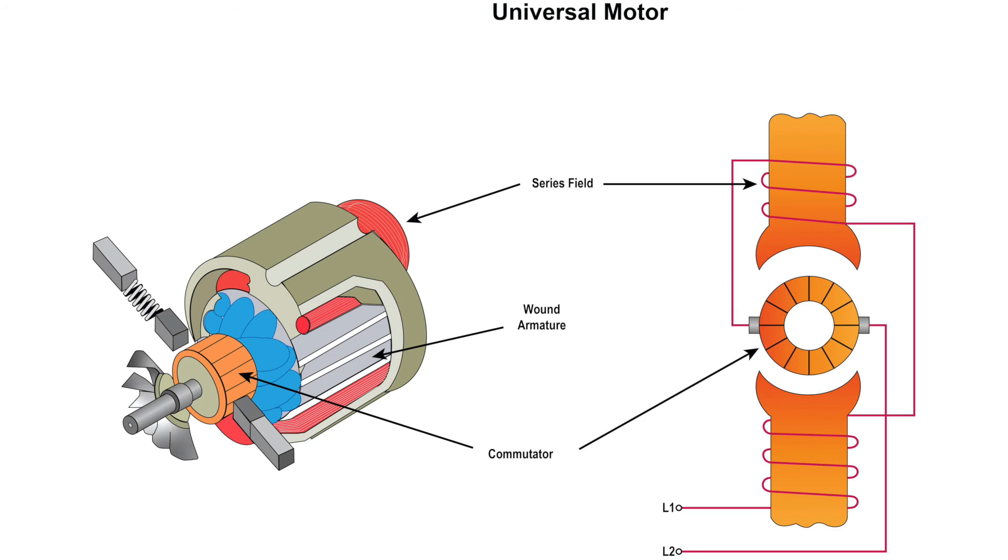Both the speed and direction of rotation of a universal motor can be controlled. Reversing the direction can be accomplished by reversing the current flow through the armature with respect to the series field. Varying the voltage that is applied to the motor controls the speed of the motor.